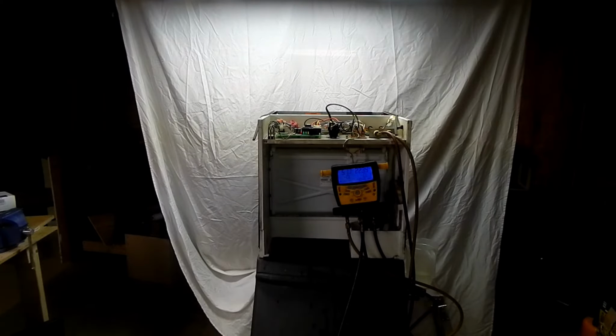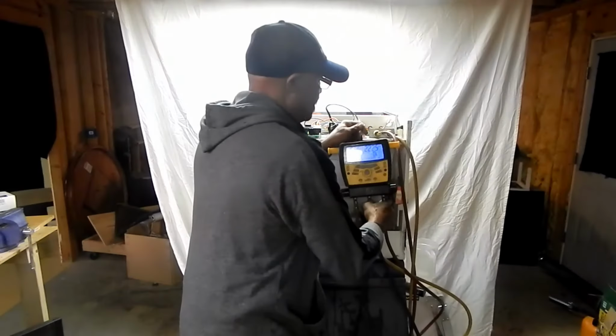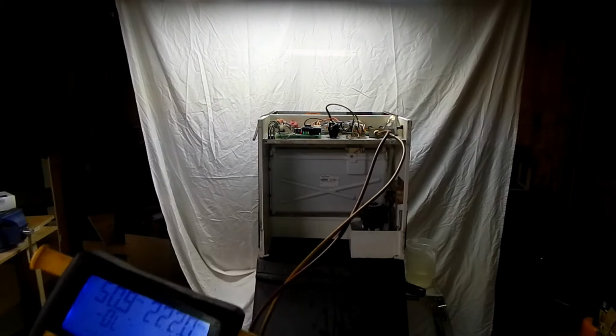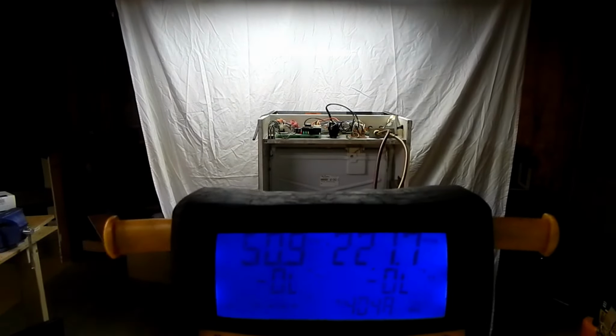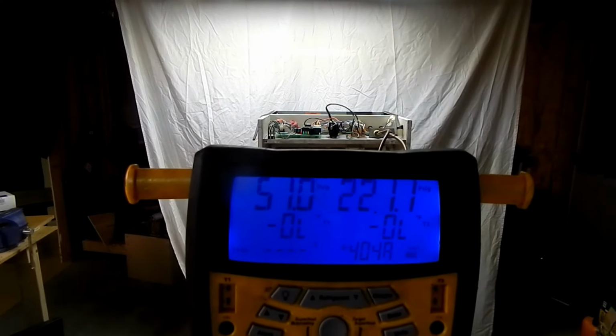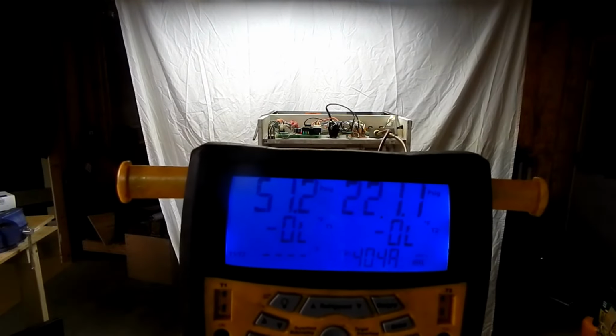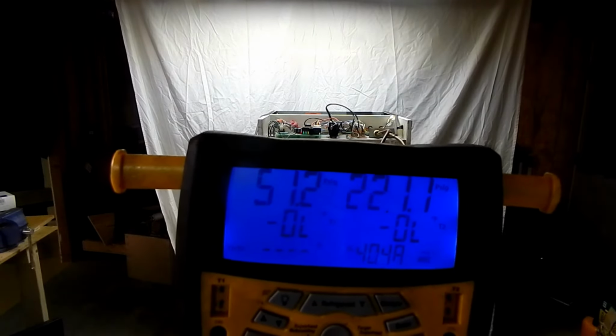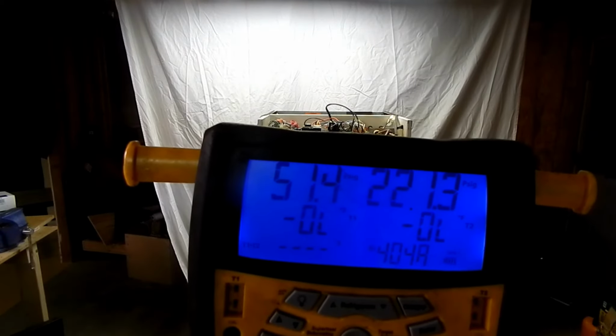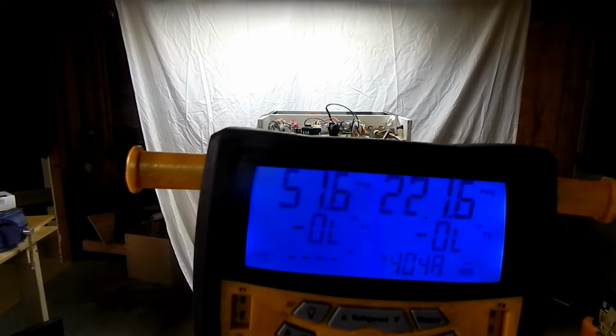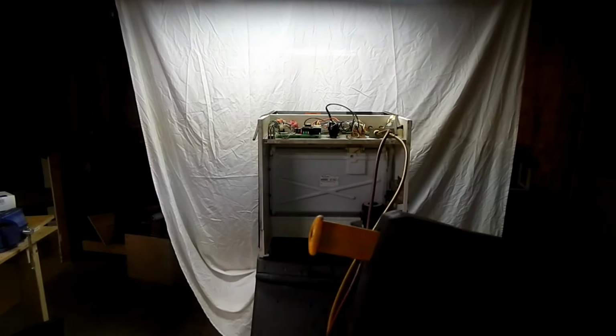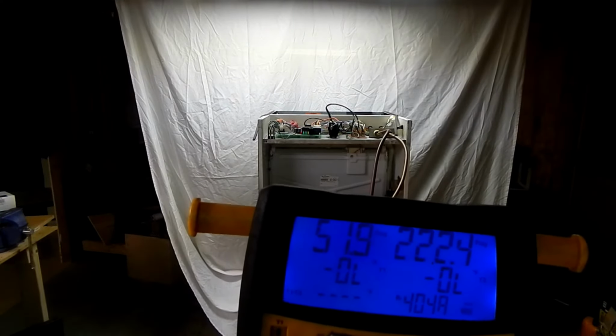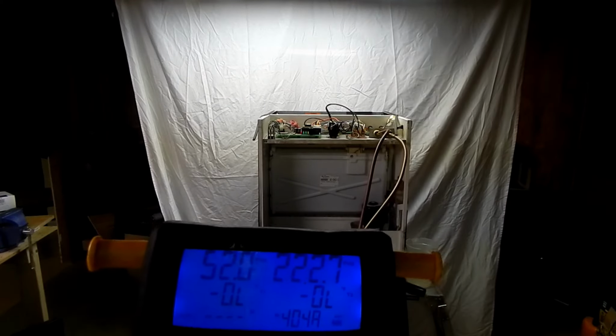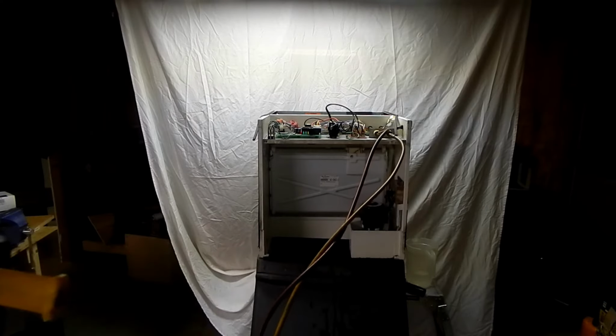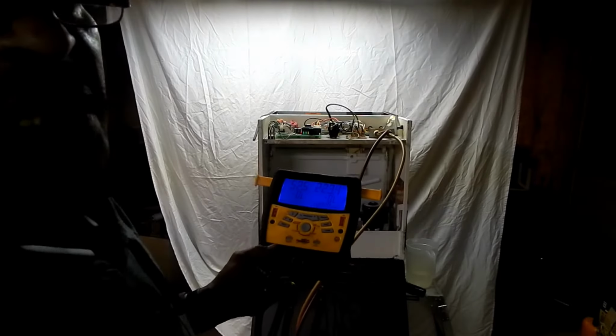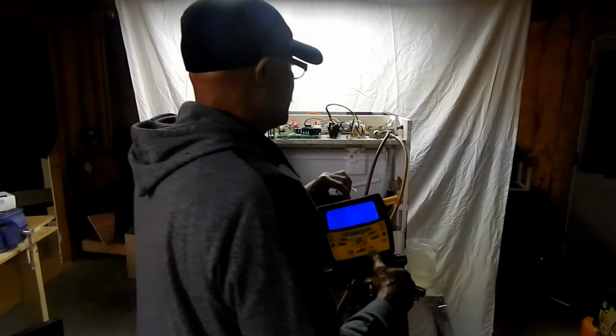Now, I got the machine on and put the gauges on. And as you can see, on the high side, it's 221. On the low side, it's about 51. And I'm looking for the low side to go down to about 23, 24. It should be making ice as that temperature drops down. And the high side will come down to maybe about 202. Well, we'll see. Each compressor is different. The pressures are different. So we'll see what this one does. But it appears that it does have refrigerant in it, so it should make ice. So we'll see. For about 20 minutes.